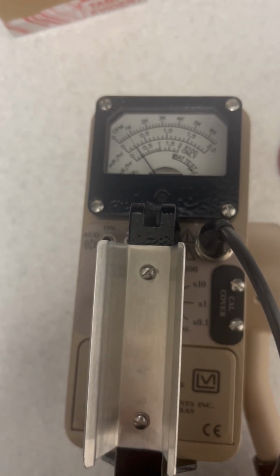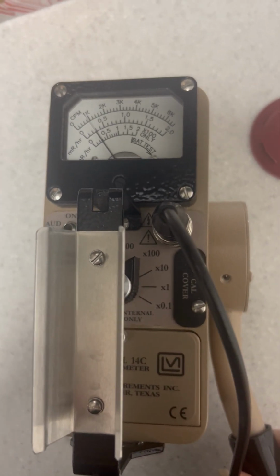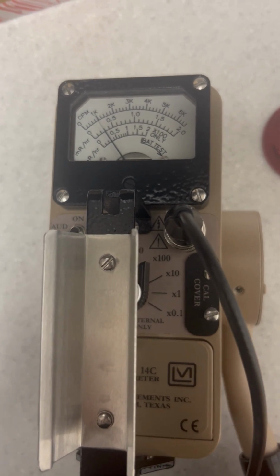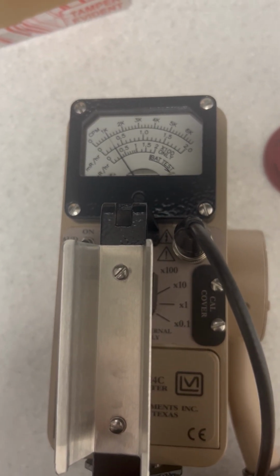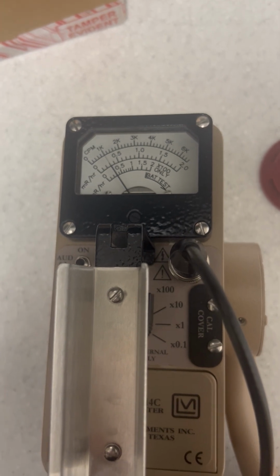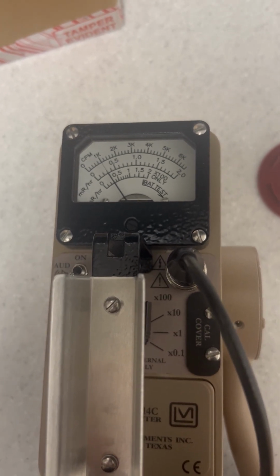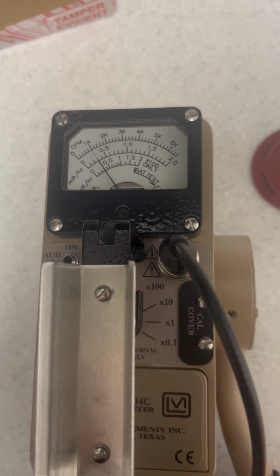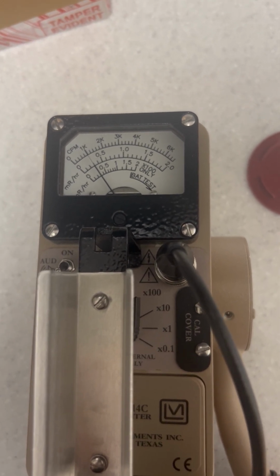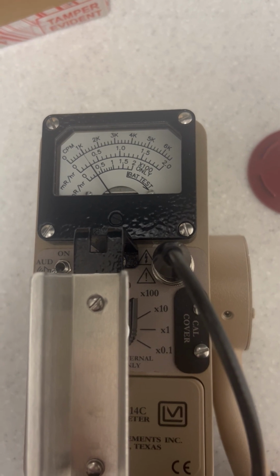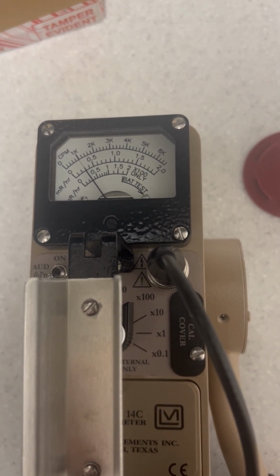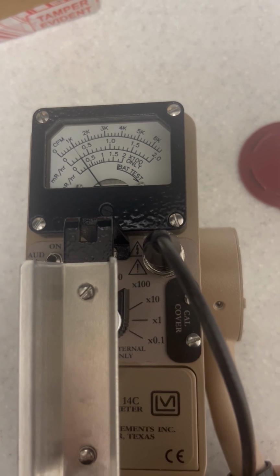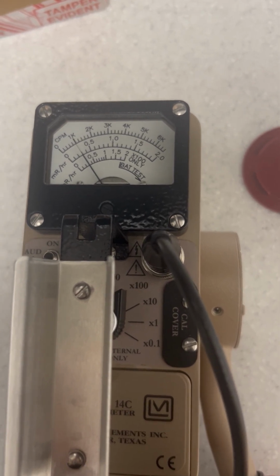So now we go all the way up to the top. Okay, now we have it times 100, and now it's able to read. So it's reading at 0.3 on the meter. We multiply that by 100, so that comes out to 30 mR per hour. And that translates to about 1,000 counts per minute if you look at the meter.